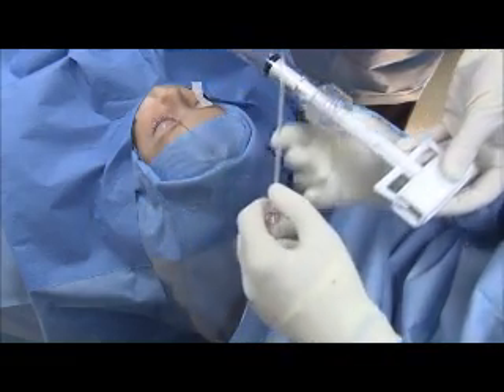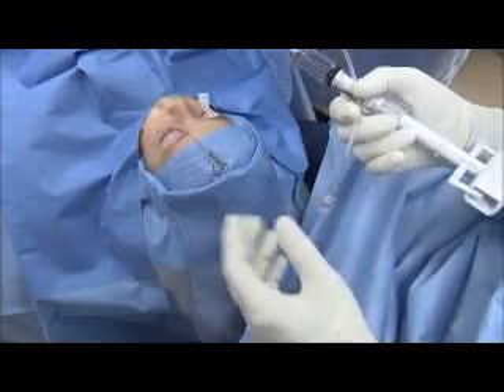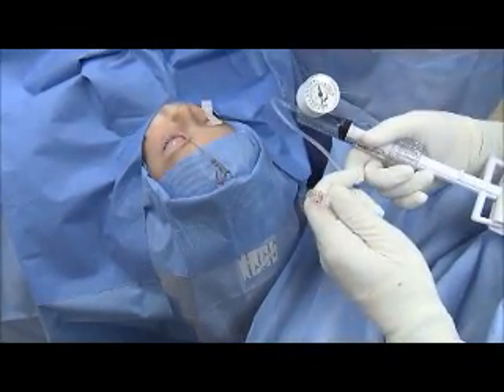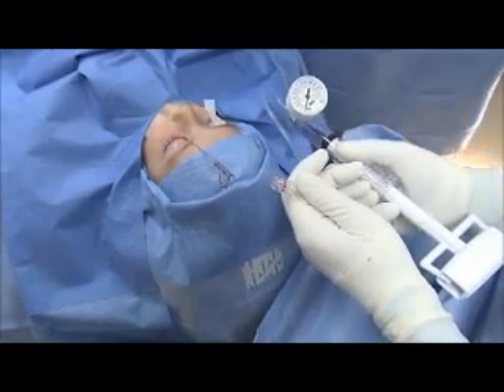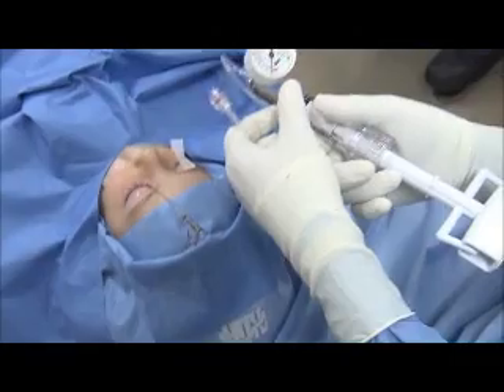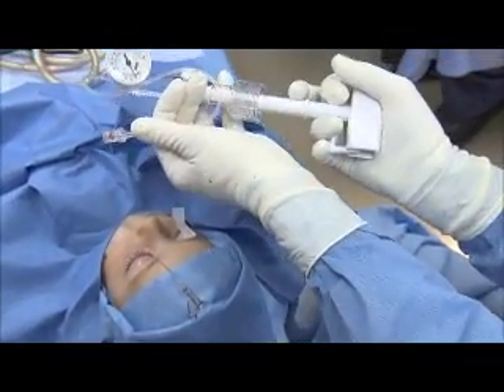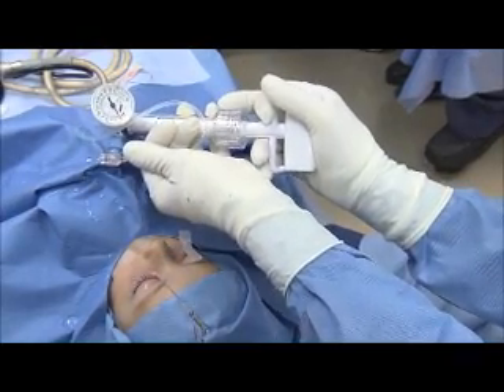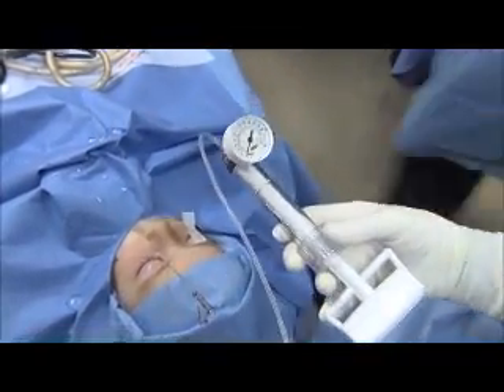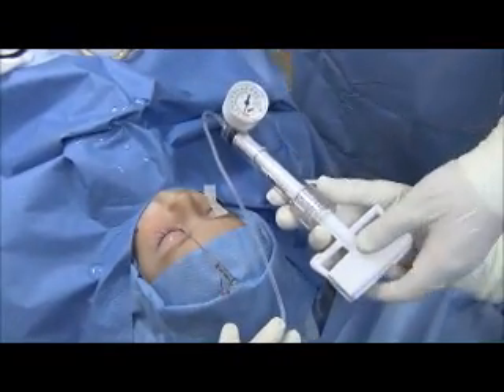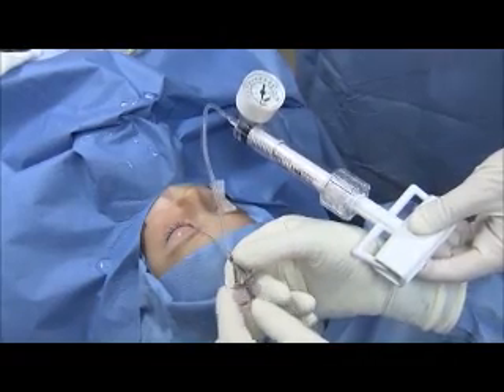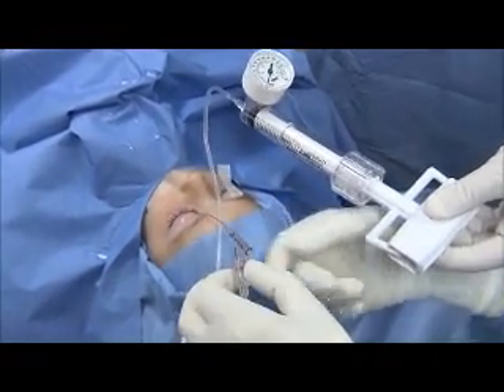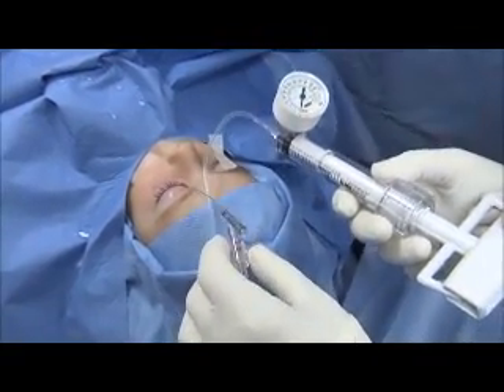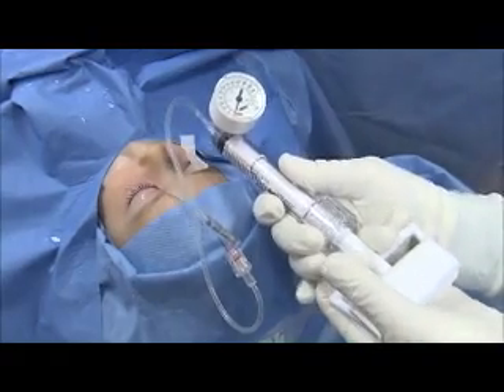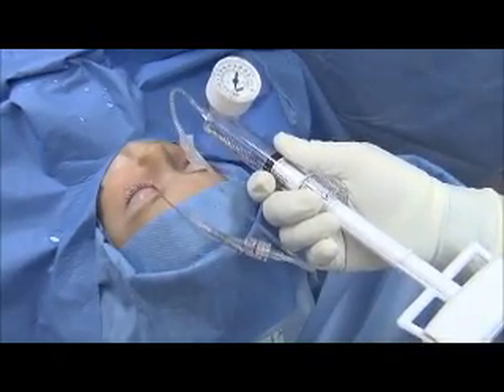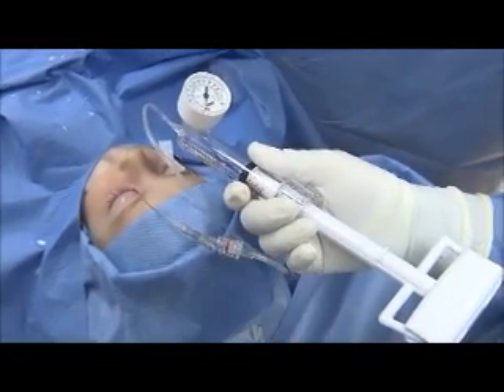Now, prior to removal, the fluid does not all passively come out of the balloon, so we need to suction it out. The inflation device is also a marvelous deflation device. So the first thing we're going to do is pull the lever, squirt out all the fluid. Then we're going to reconnect the inflation device, which is now the deflation device, to our inflation port. Now we're going to pull the lever, and we're going to suction back all the way and hold. And we can let go, and that's constantly deflating the fluid out. And you leave that for about 10 seconds.